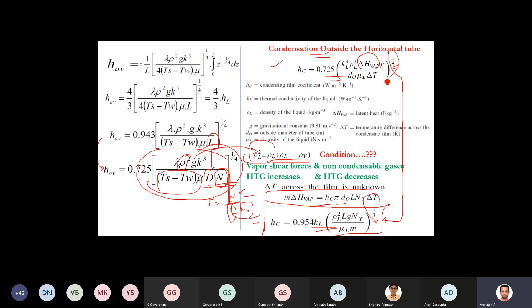The number of tubes in the vertical row is to be corrected: Nr power minus 1 by 6. This Nr is approximately 0.78 times ds by pt, where ds is the shell diameter and pt is the vertical tube pitch. You know this pt is pt dash for square pitch and 0.87 times pt for triangular pitch. Those things you will apply, you know already. Now this is the correction factor introduced for a series of tubes.